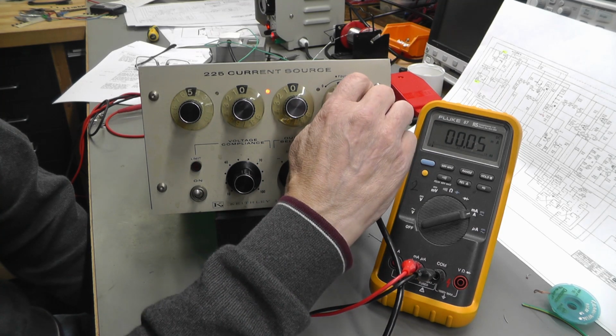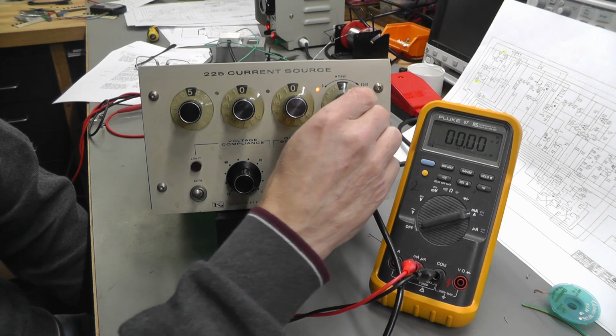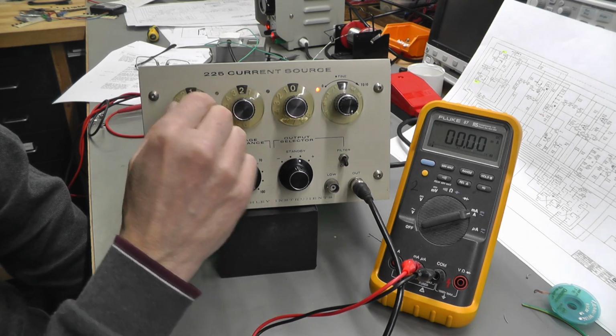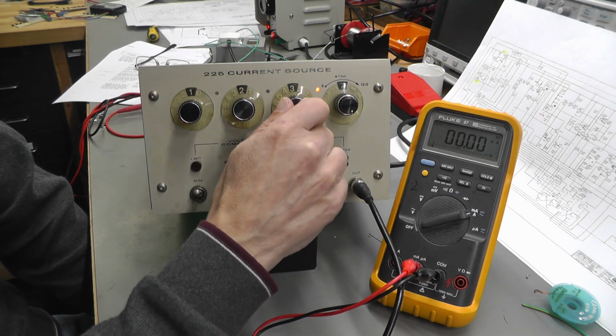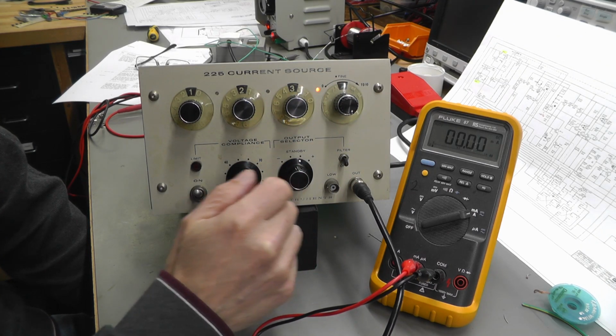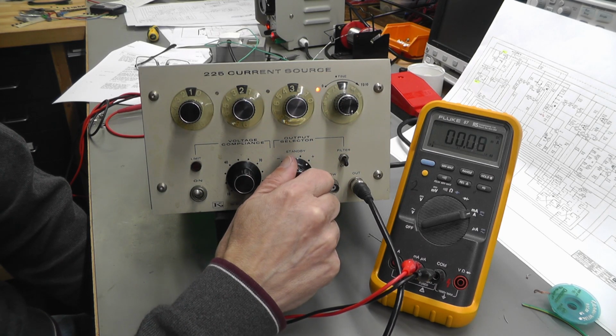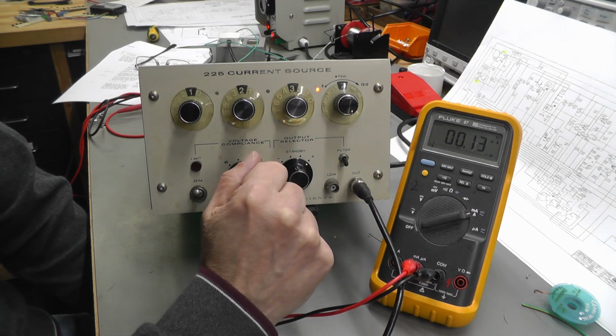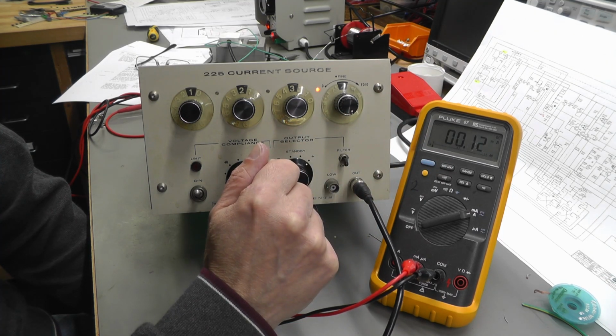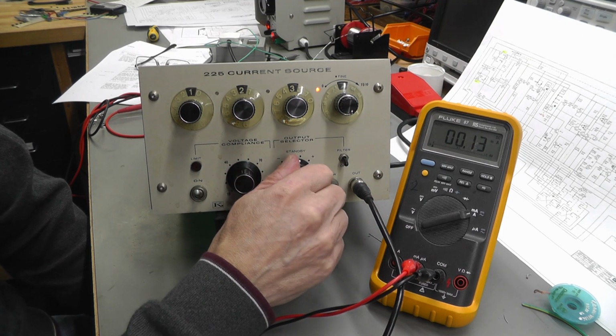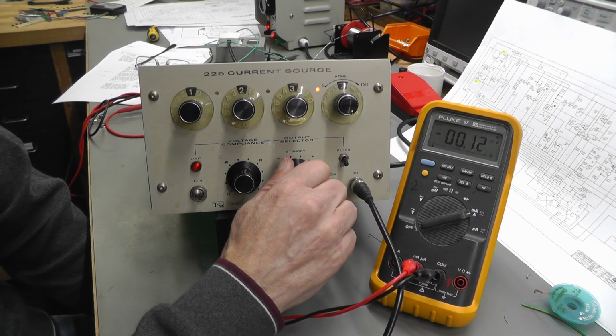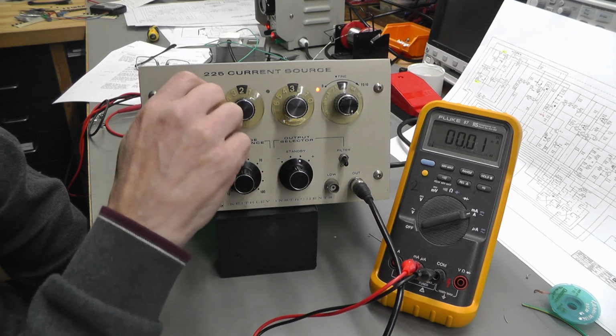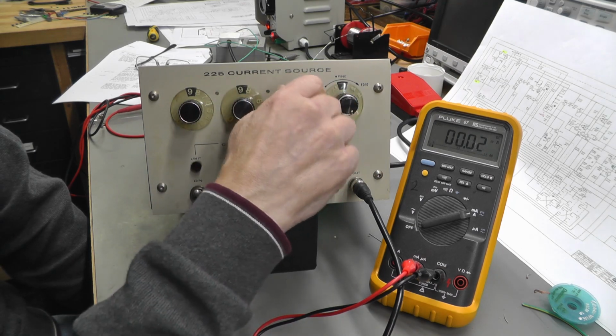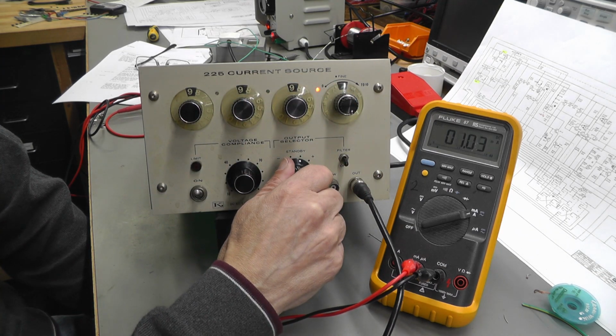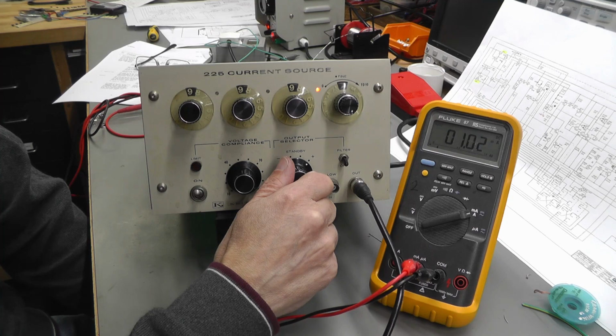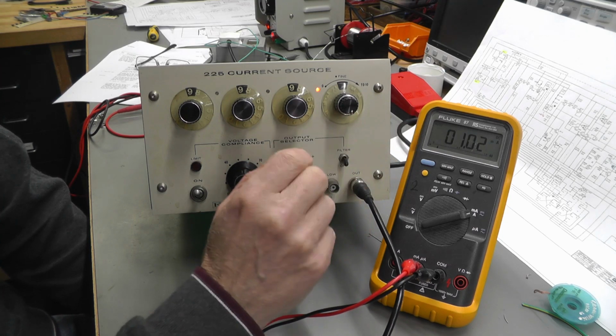Okay, let's see if we can get something out of the microamps. So this time we'll go to 123 microamps, let's see what that does for us. Well yes, run out of resolution on the meter, but looking good. And on the negative direction, yep. Let's wind that right up to 999. Yes, 1 milliamp, again reading slightly over.